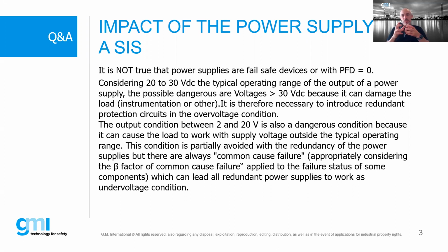You can avoid this situation by introducing redundant power supplies, but you must also take into account common cause failures, and I think you are aware of the beta factors. Same instrumentation, same devices in a redundant system made by the same manufacturer with the same typology, same batch, can fail at the same time. So this is also a risk. And in the case of redundancy, if one power supply connected in parallel is working between 2 and 20 volts, it can lead all the power supplies to work in the same undervoltage condition. So there are different situations you can have on your system.